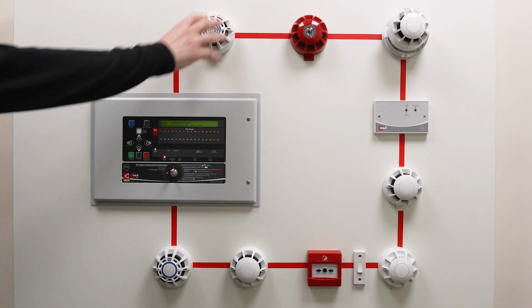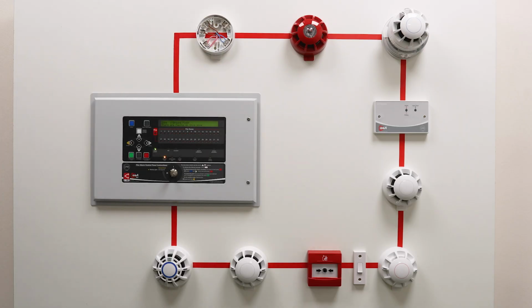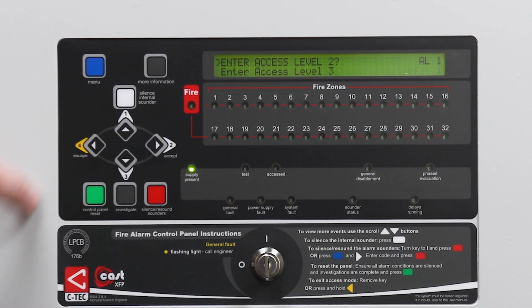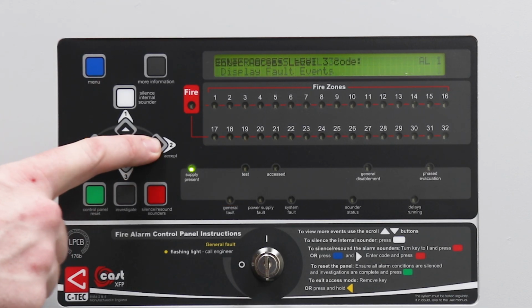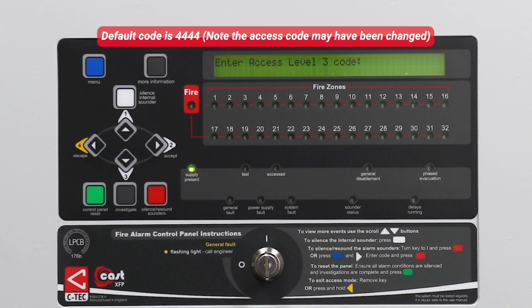First, locate and remove the faulty device. Then, back at the panel, press the menu button, scroll down to access level 3 and press accept. Input the 4-digit access code. The default for this is 4444.